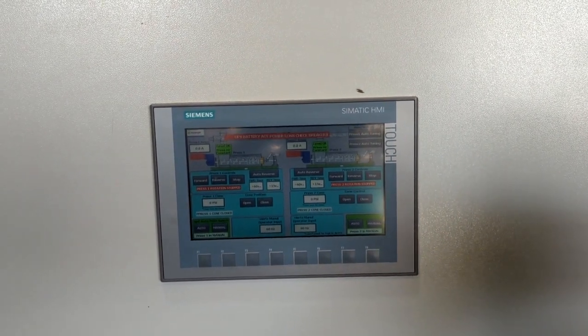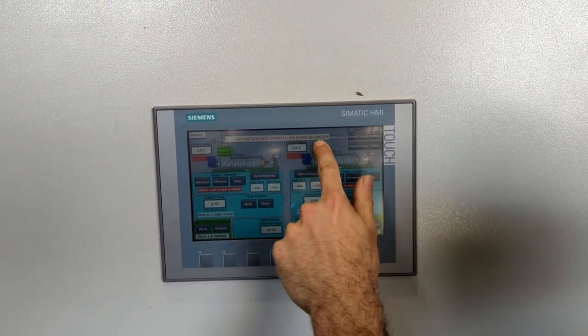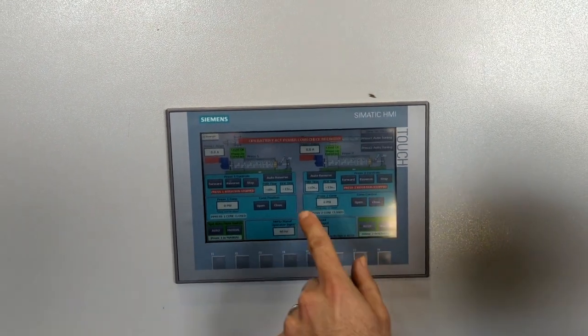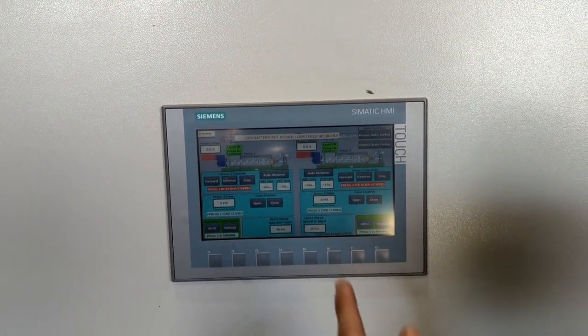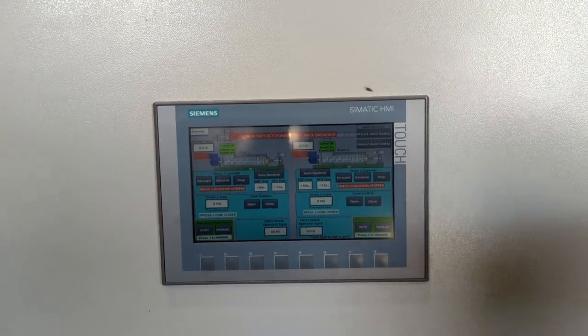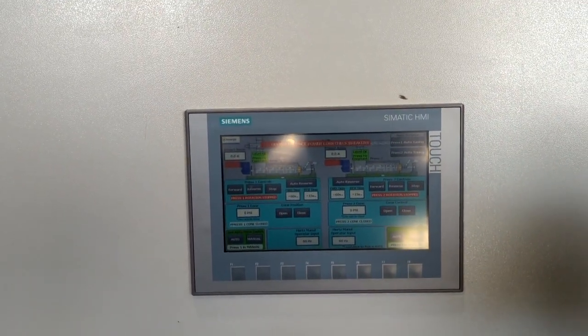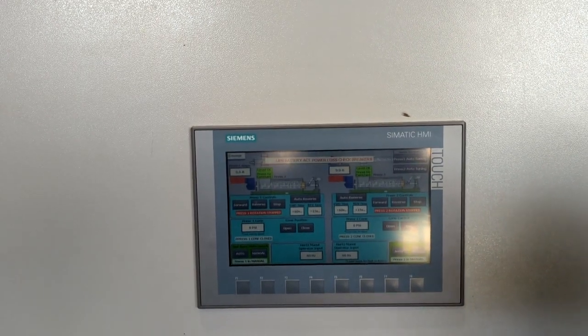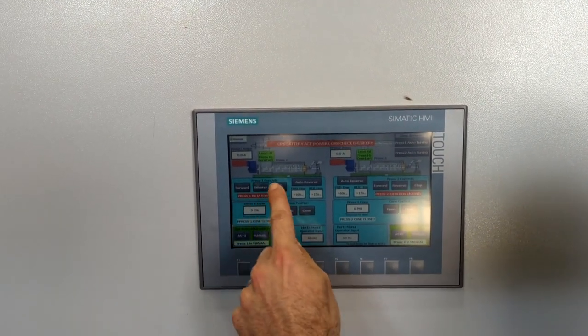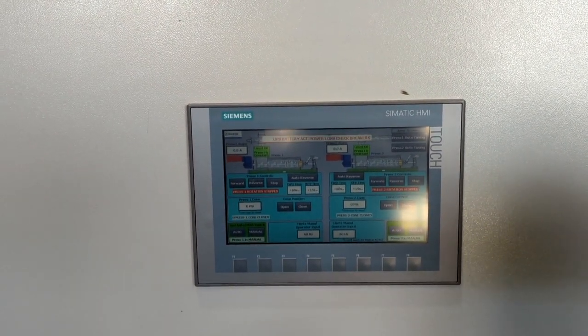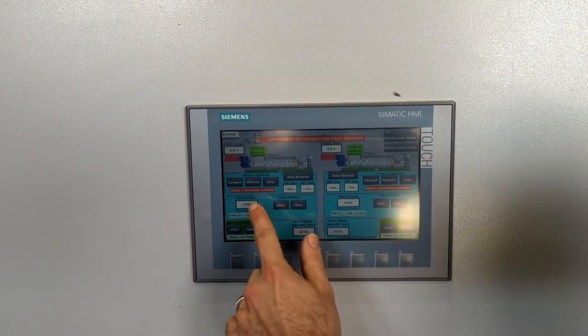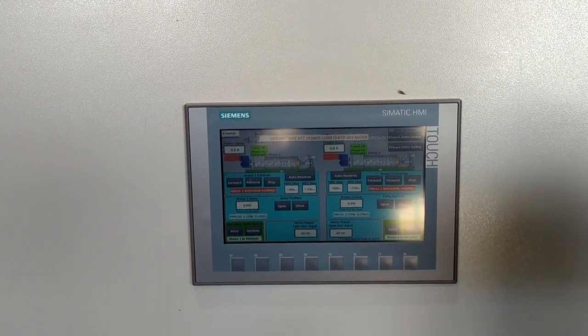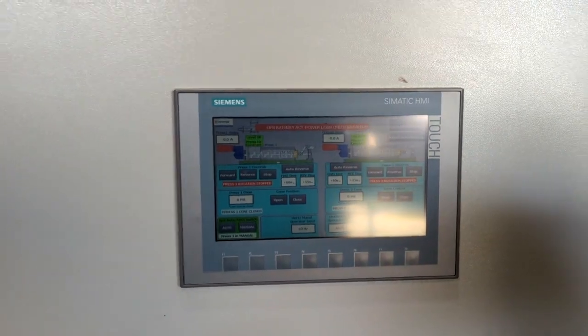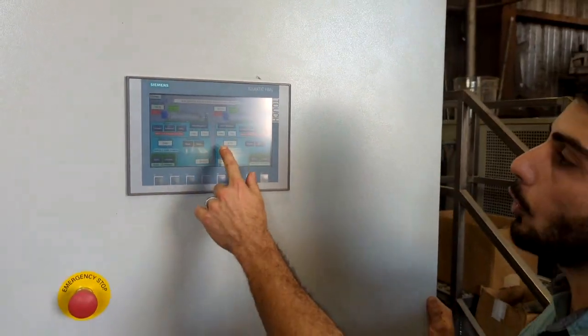See right there, UPS is activated, the main breaker has been disconnected, so it's letting you know that the battery is taking effect, and we have our PLC still powered up even though the main breaker is off. We have forward, reverse, stop, manual controls for each one of these presses. We're also controlling all the actuators and all the pneumatics associated with these machines. We're controlling the cone pressure and the cone position.